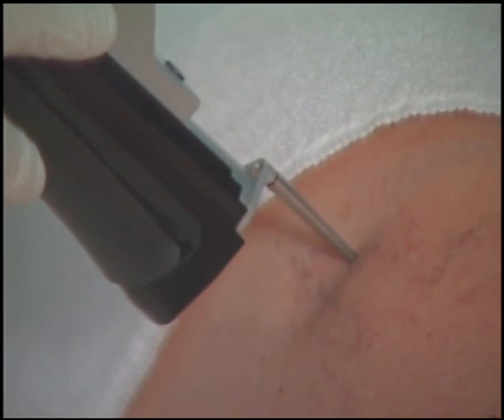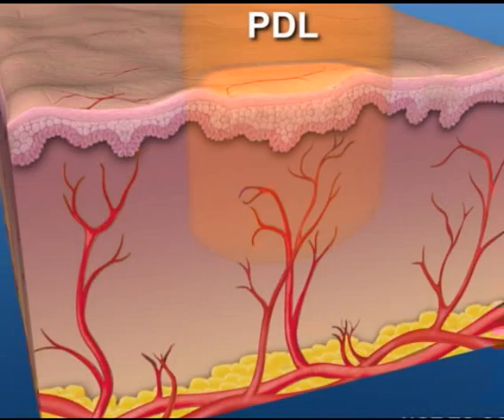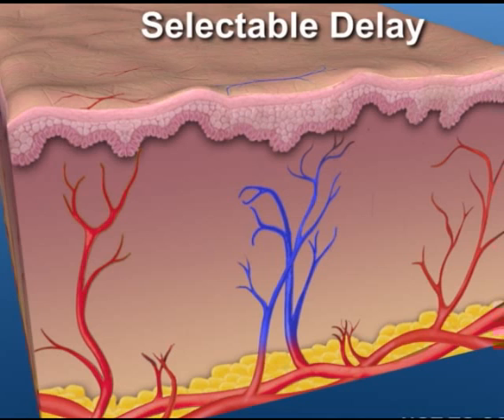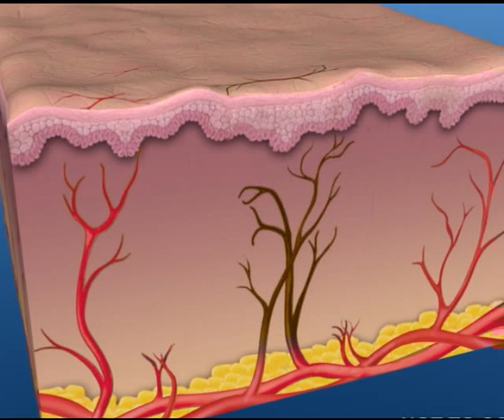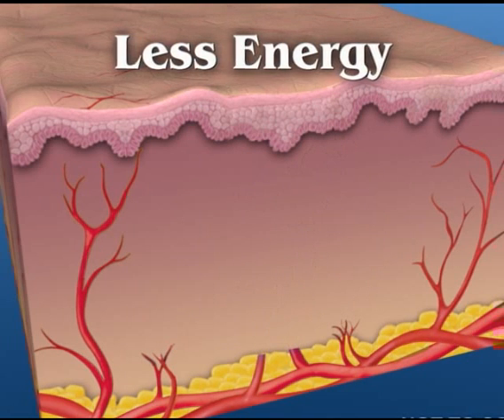The groundbreaking Cynergy with MultiPlex option enables sequential emission of the pulse-dye laser and the Nd:YAG laser from the same delivery system. The first laser pulse of the pulse-dye laser heats the blood, creating a clot and altering the color. The Nd:YAG laser pulse is then absorbed three to five times better by the target, requiring less laser energy to destroy the target.